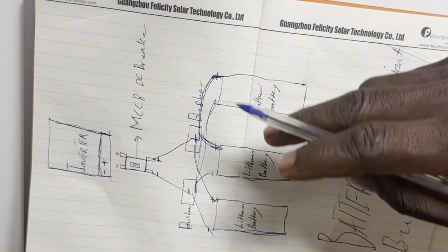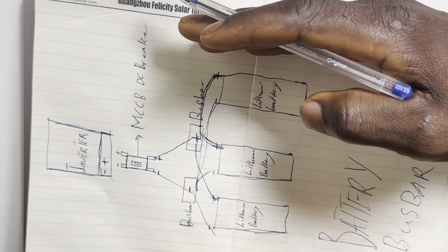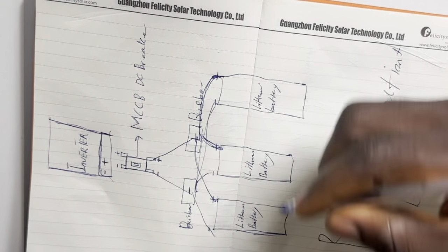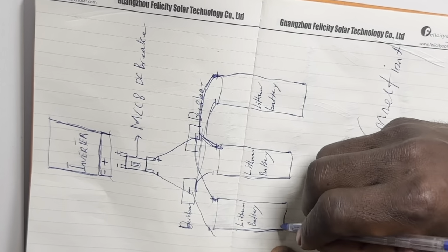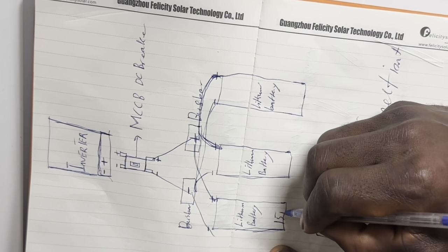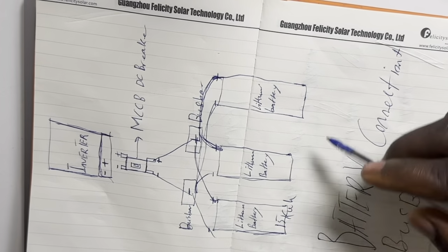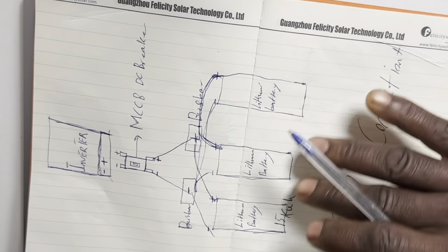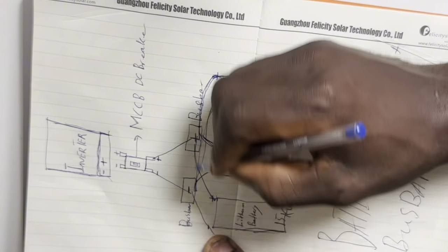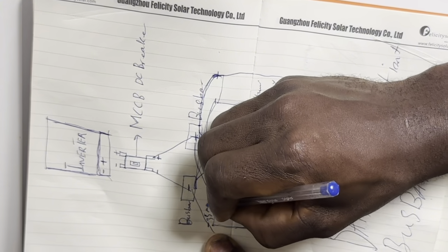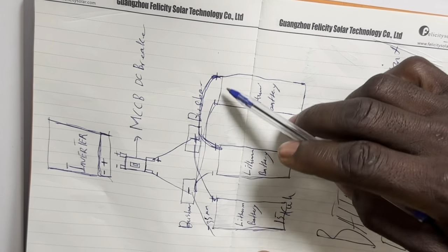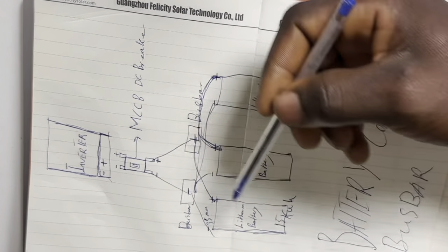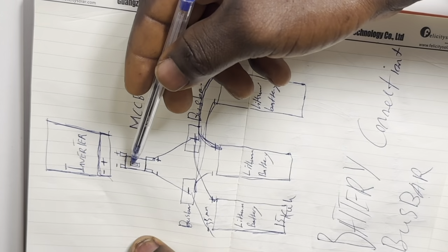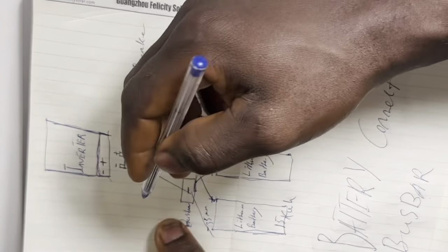If you have a bus bar with 3 units of batteries, say these are 15 kilowatt-hour lithium-ion batteries, and the cables used for each battery are 35mm cables connecting to the bus bar, then coming from the MCCB breaker to the bus bar, you need to use a bigger cable size - say 50mm.